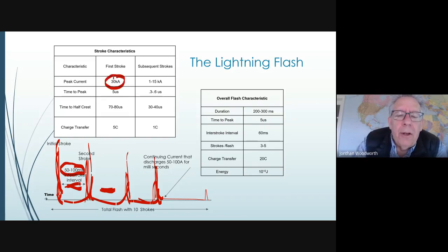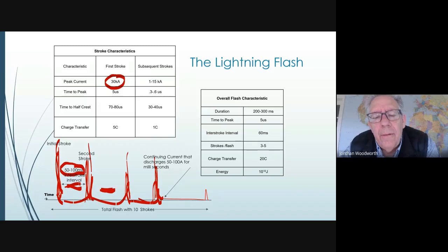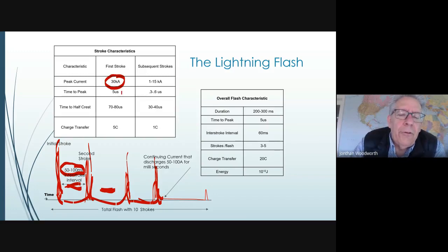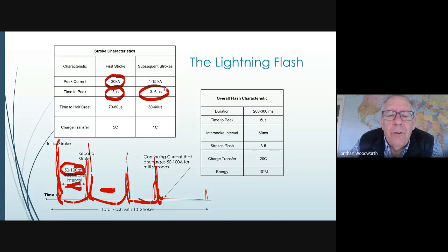The other important thing is that the average peak current of a lightning stroke is 30,000 amps. So when we do a lightning study, at a minimum we test to see what happens to the power system when 30,000 amps of current strikes the system. Usually we go much higher than that. You can also see that the time to crest is 5 microseconds. For the second stroke, the rise time is a little bit faster. These are numbers you need when you're trying to do surge protection of power systems.